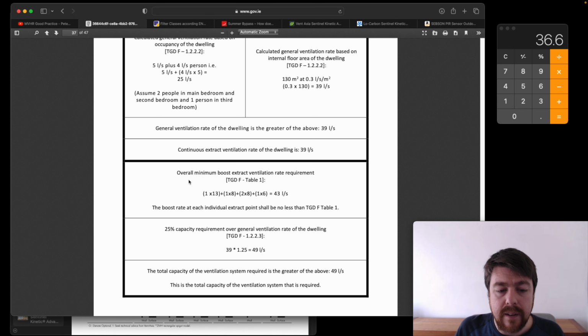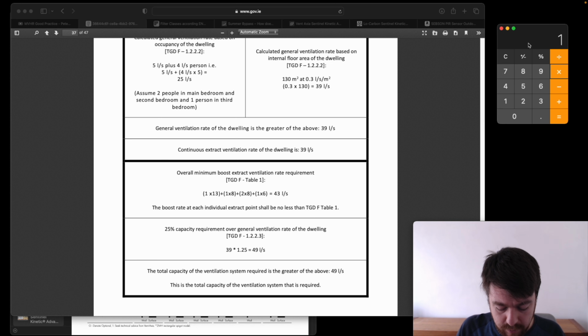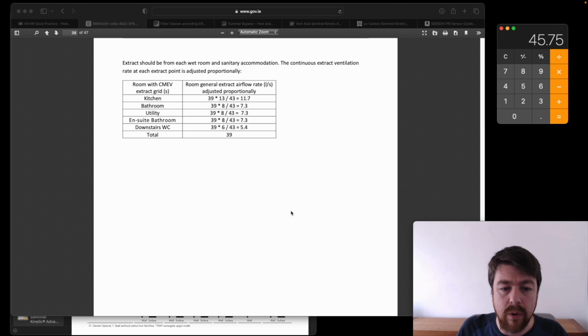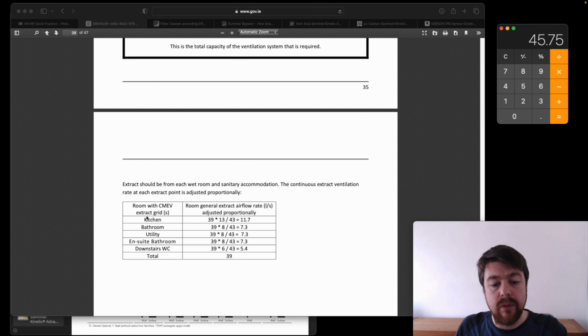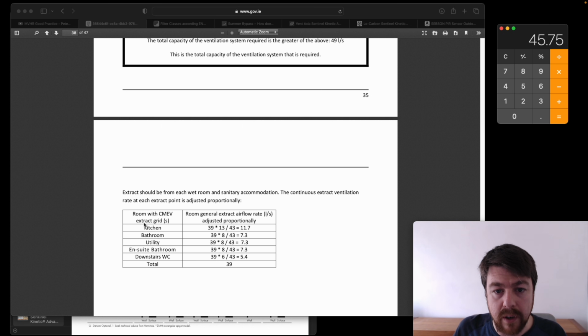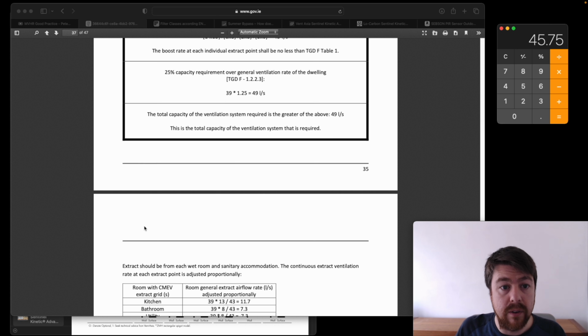They then want you to get a general continuous extract ventilation, and they want you to scale that up by 25%, basically to allow for boosting at different places. So 36.6 multiplied by 1.25 to add on 25%, that's basically coming up to 46 litres per second. So that's roughly speaking the number we need to hit. There is further guidance down below for when one is commissioning the system, as to what proportion of litres per second should go through each room. But for now, let's not worry about that. We just need to choose the overall unit itself.